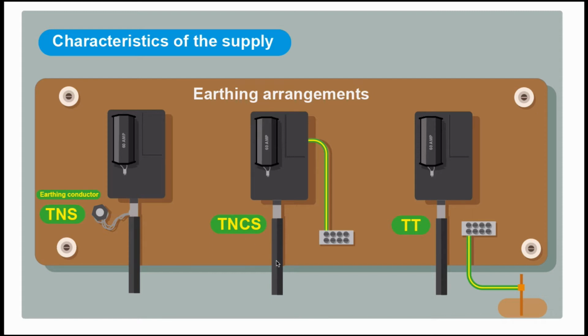We have TNCS. This is where the neutral and the earth in the supply cable are combined. This is external to the property. And when it enters the property, the neutral and the earth are separated, TNCS, combined and separated. So the neutral is used as your earth return path.